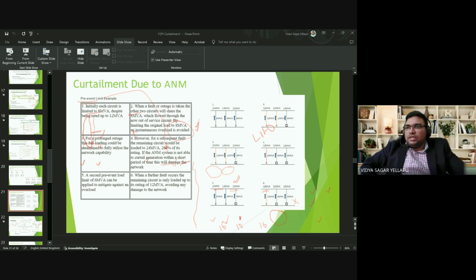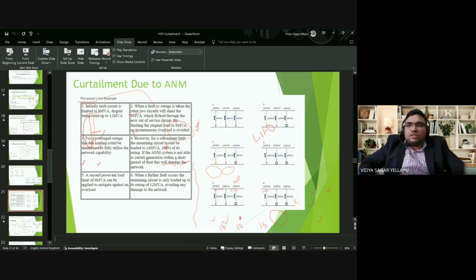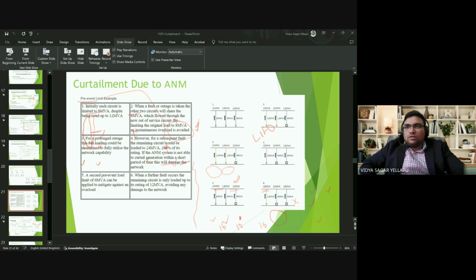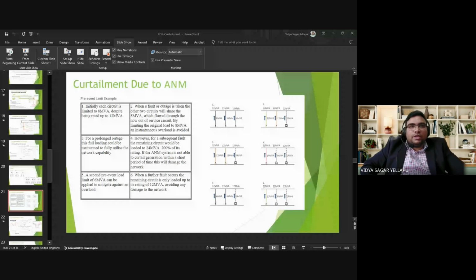So it adjusts the limits for these assets to 6 MVA. In that case, the ANM system adjusts the generation such that these carry 6 MVA pre-fault, so that if there is a fault, then the assets carry 12 MVA, which is as per the rating of these assets. That is the concept of this n minus 2 scenario of this ANM.